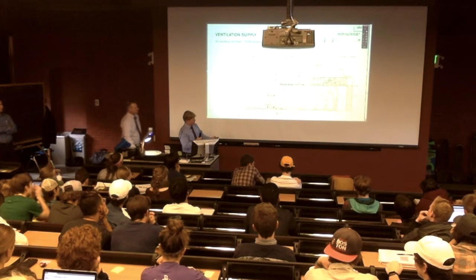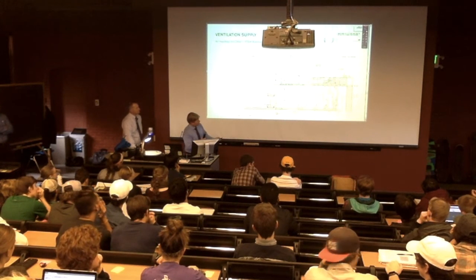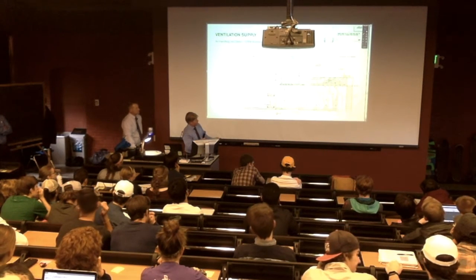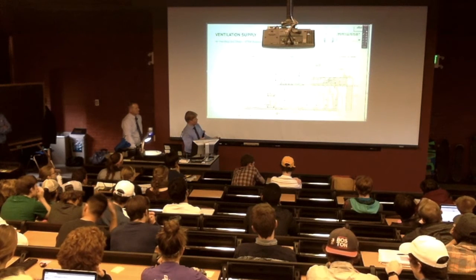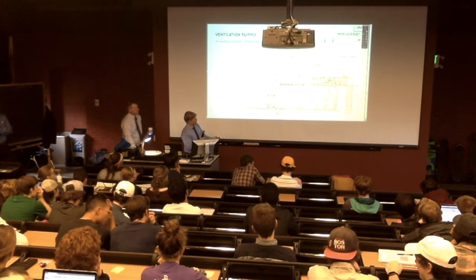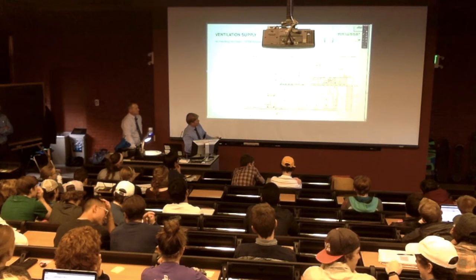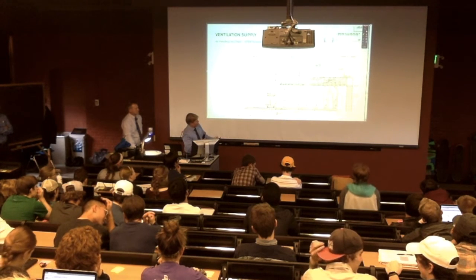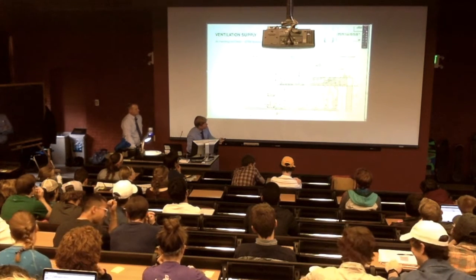So supply comes in this side. We hit first a set of filters. Filters will keep your air clean, and there's a code requirement for that. But the first big set of coils that we hit is the heat recovery coil, which I think is this guy.